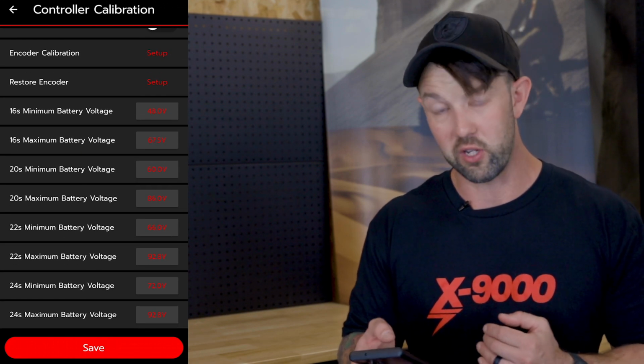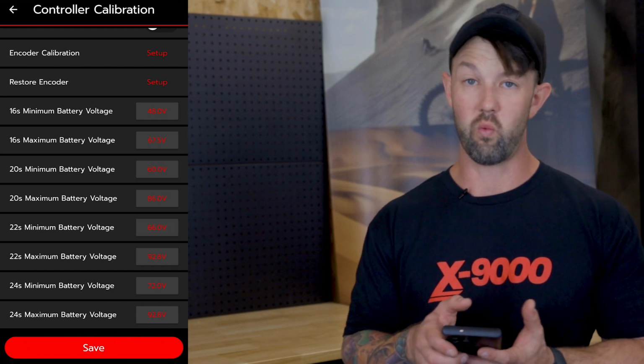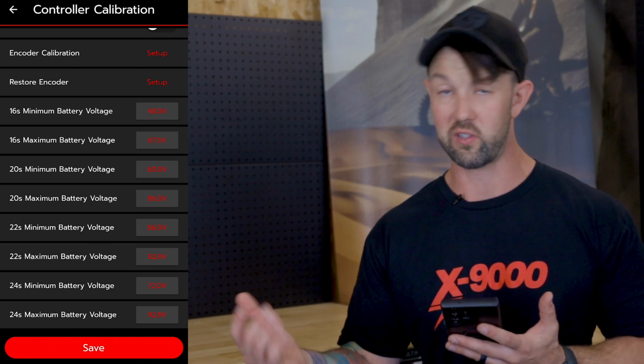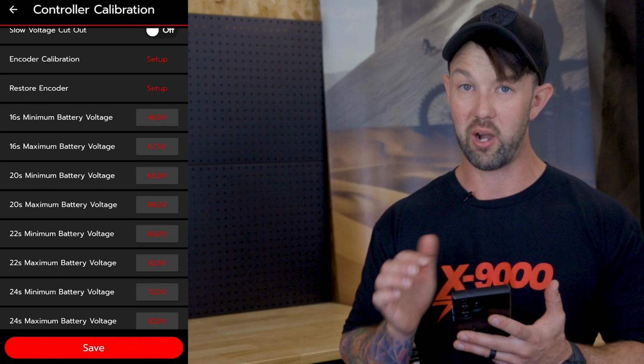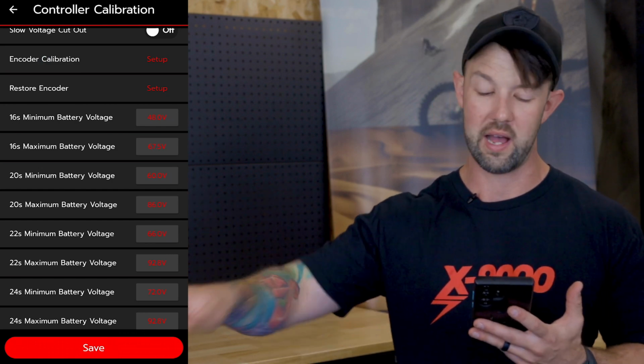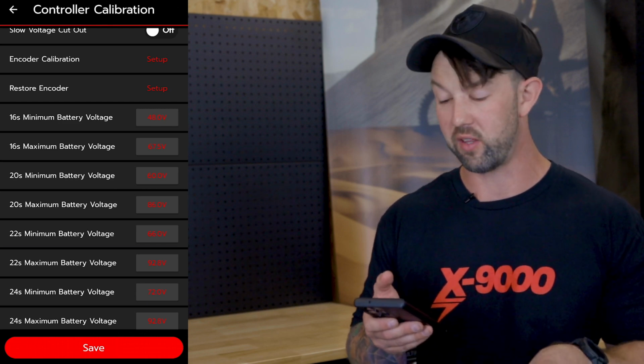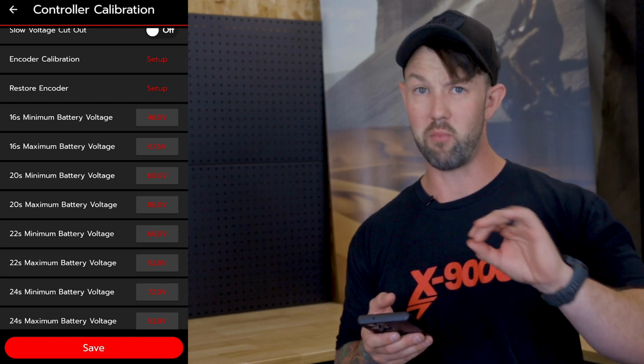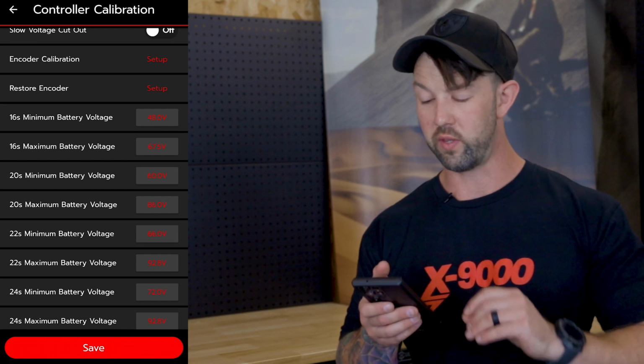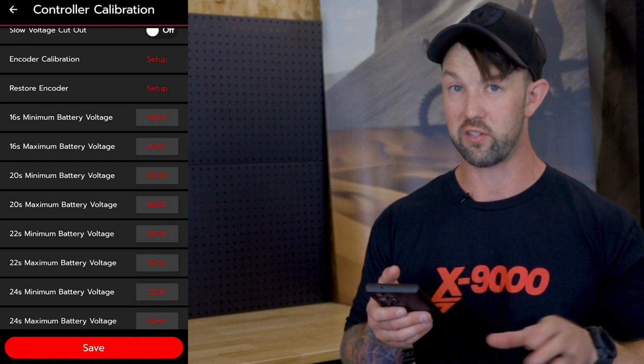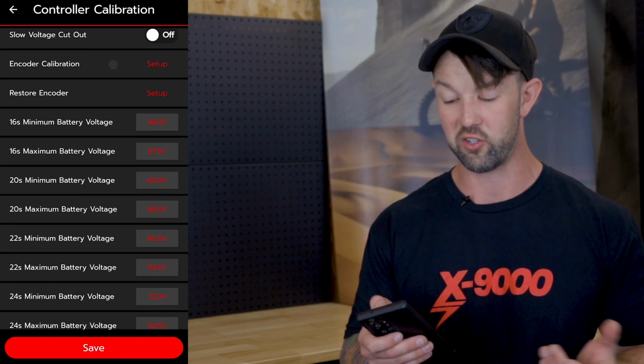Following that down, we've also got the encoder calibration. If you have a Hall sensor motor selected, this will come up as Hall calibration, but because we're on MX4 here, this now comes up as encoder calibration. This is where you would physically calibrate the motor. If you ever loaded a motor XML, after loading it you would need to run a Hall sensor or encoder calibration, and you'd come into this section to do it.